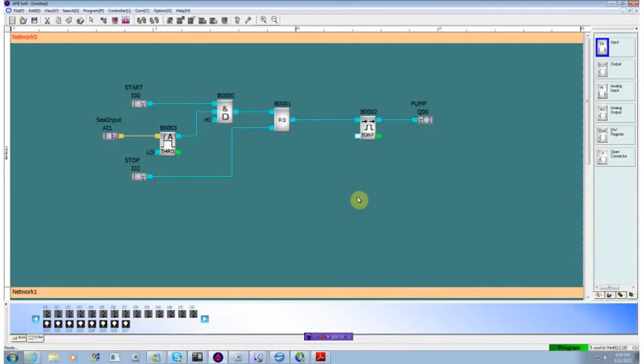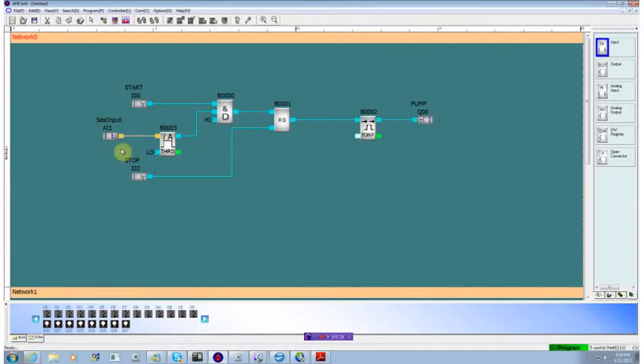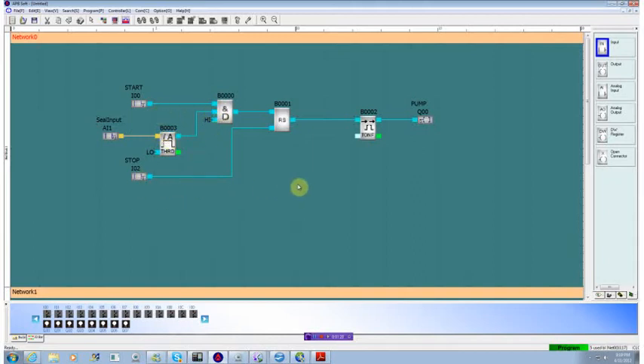This is the application that we've put together so far. There's a start button that latches on a latch that starts a timer and turns on a pump. There's a seal leak detector. This analog value has to be above a certain level before the start can activate the pump. And there's a stop button.